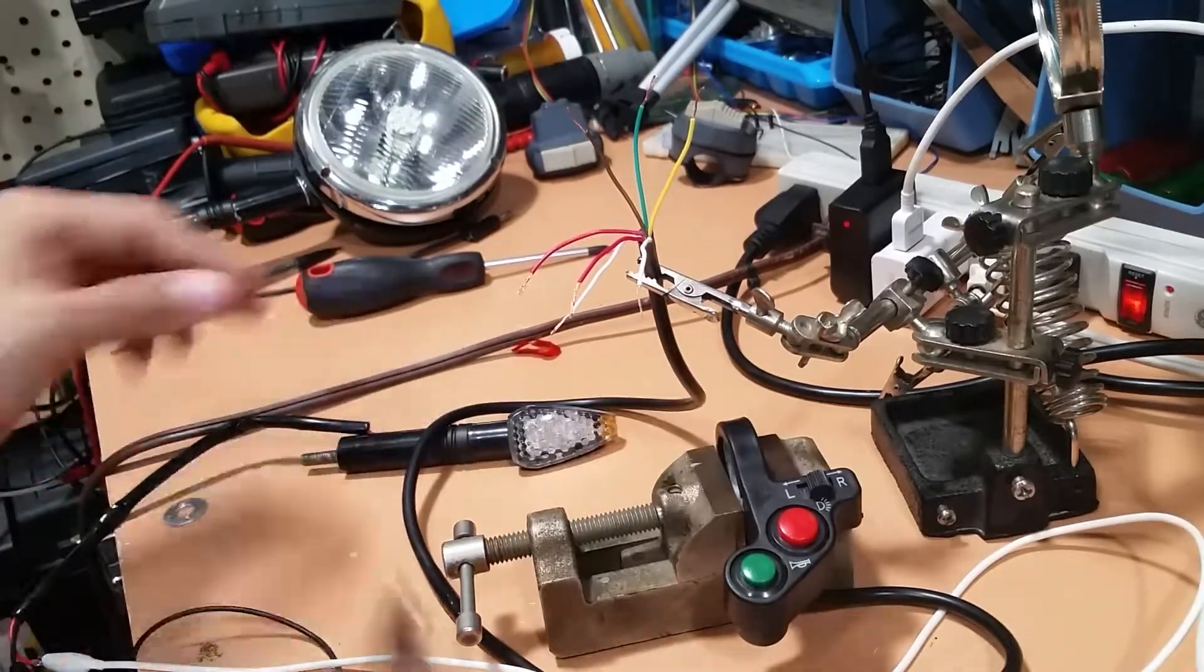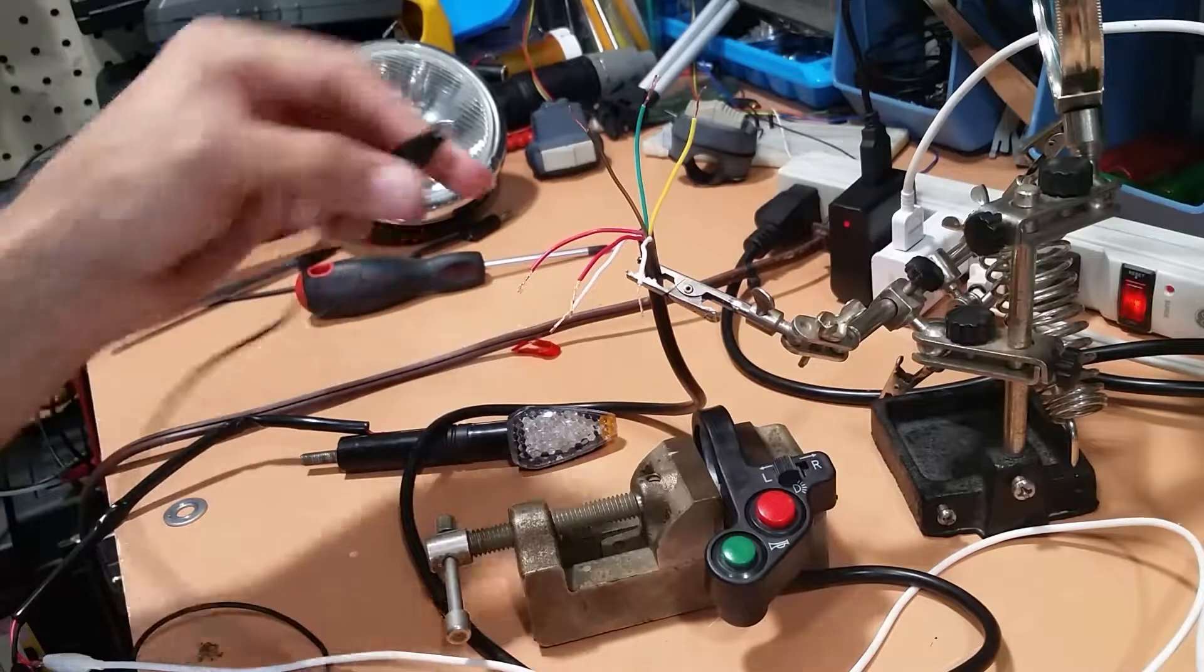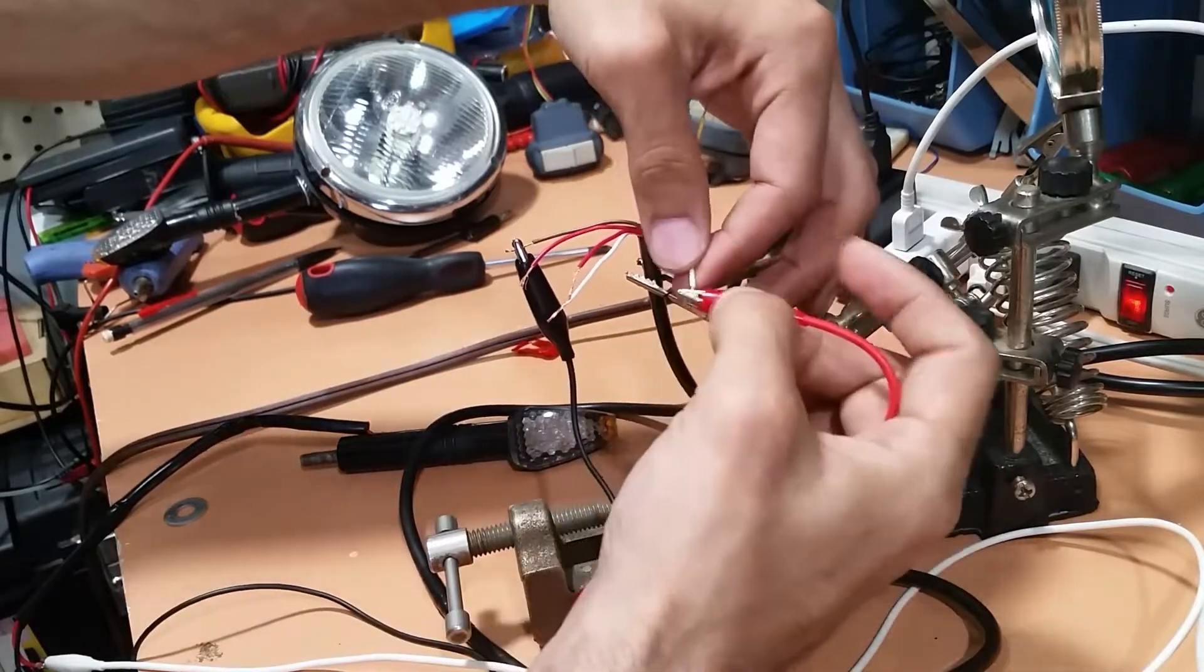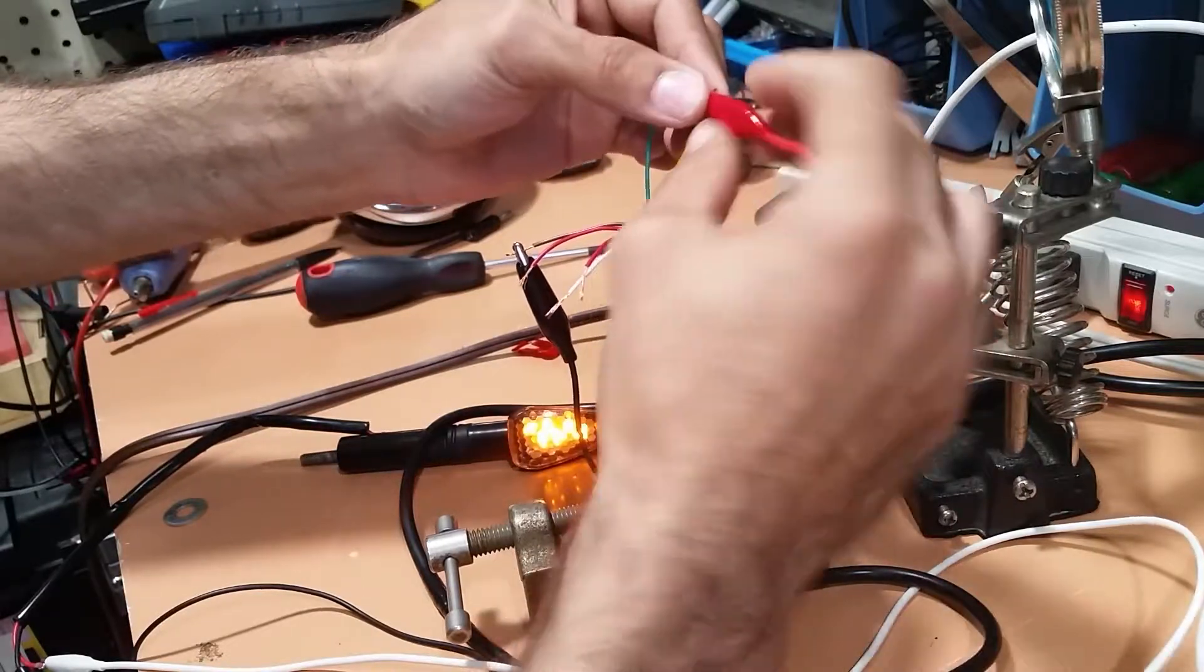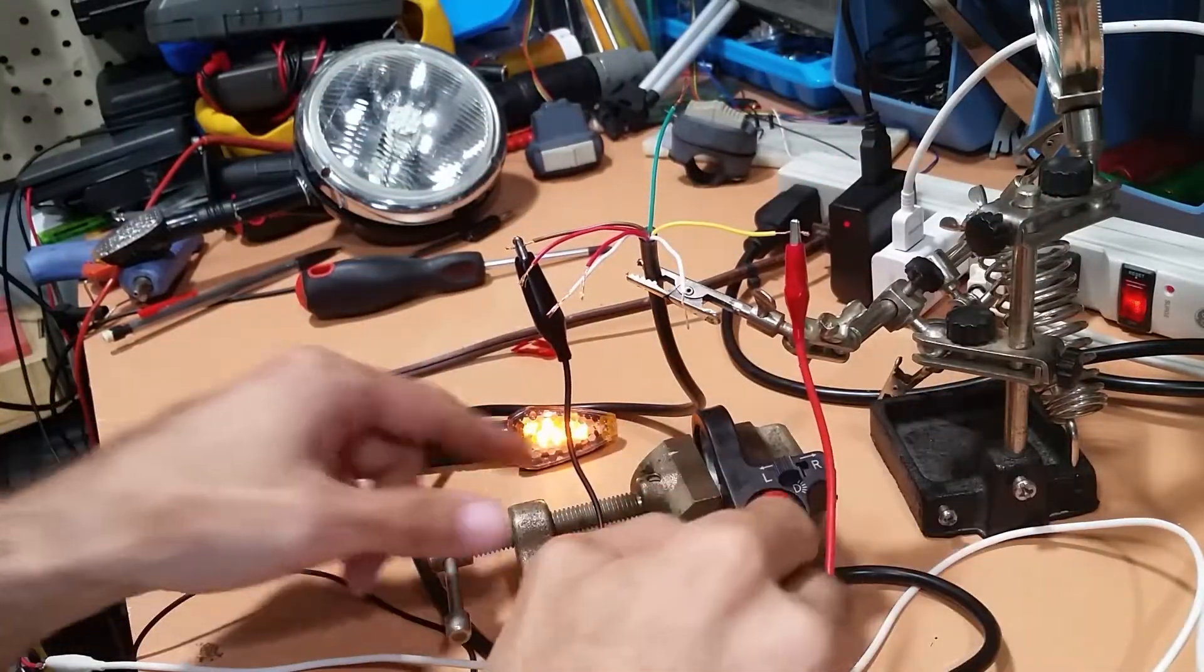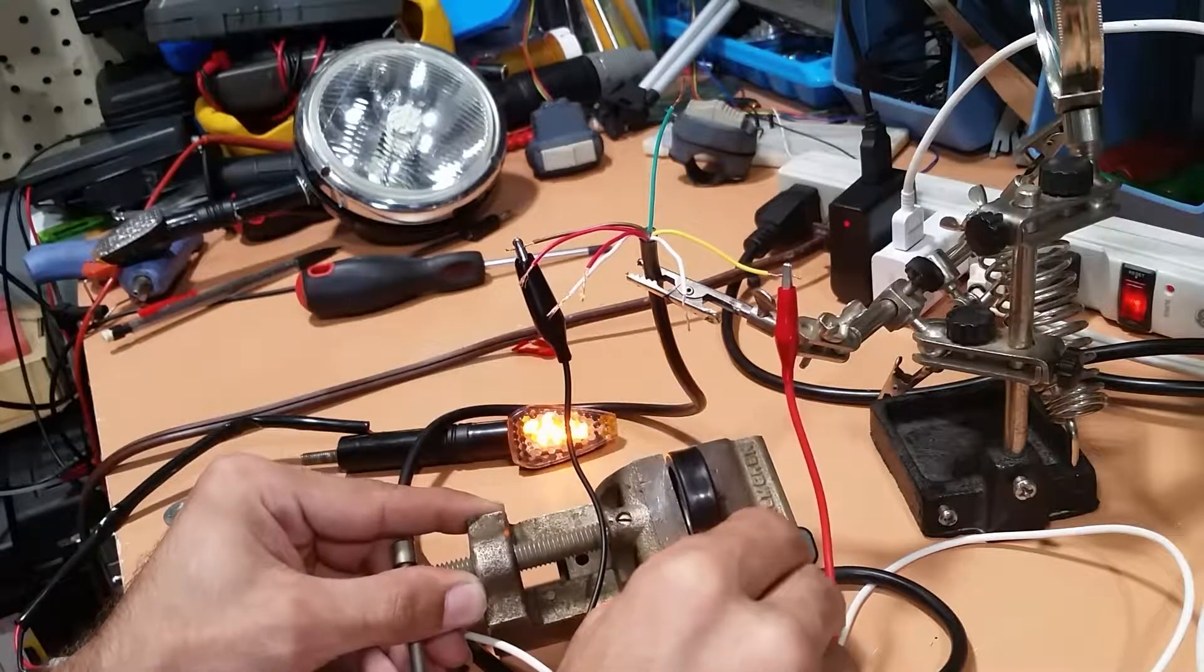So let's get one of our probes. First off, let's switch this over to the left signal indicator. We'll hook up one of our probes to brown and we'll just go through the sequence. White, nothing. Let me try to get into a better view so everyone can see. White, nothing. Red, nothing. White, nothing. Green, nothing. Up yellow, we have contact on brown and yellow.